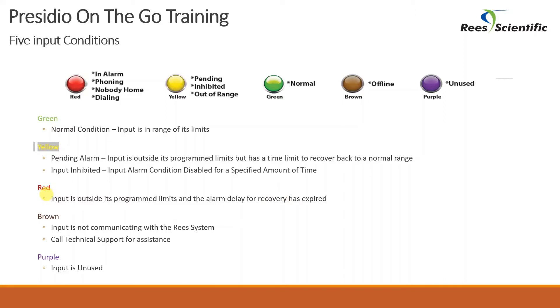When you manage this alarm to inhibit the input that is in alarm, it will turn back to a yellow condition and show that the input has been disabled for a specific amount of time. Another condition is the purple or unused condition. This is mainly when a unit is placed out of service or taken out for repair. During this time no data will be collected for this input. Lastly, we have a brown input which is a communication error. This means there is nothing wrong with the unit being monitored but there is a problem with the Rees hardware communicating back to the main Rees computer system.